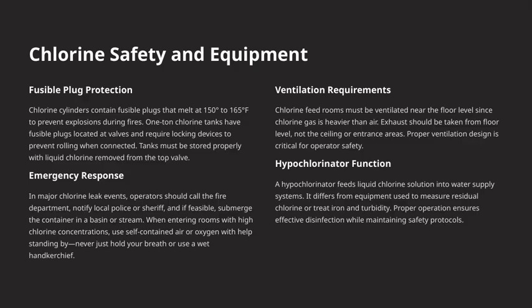Moving on to emergency response. If there's a major chlorine leak, the first step is to call the fire department immediately. You should also notify local police or sheriff's office. If possible, submerging the leaking container in a basin or stream can help contain the leak. When entering areas with high chlorine concentrations, always use self-contained air or oxygen supplies and have help standing by. Never just hold your breath or try to use a wet handkerchief. That's not safe.